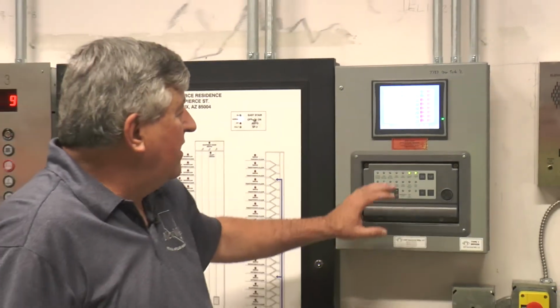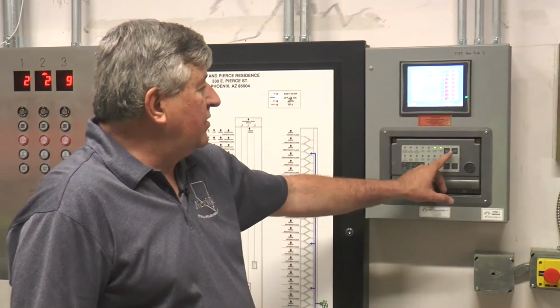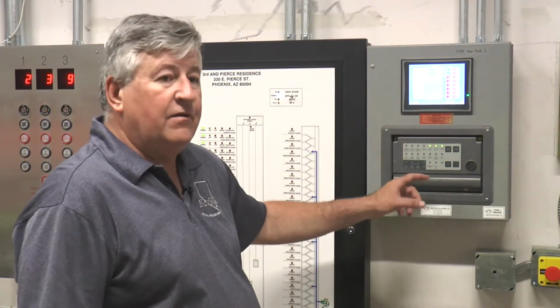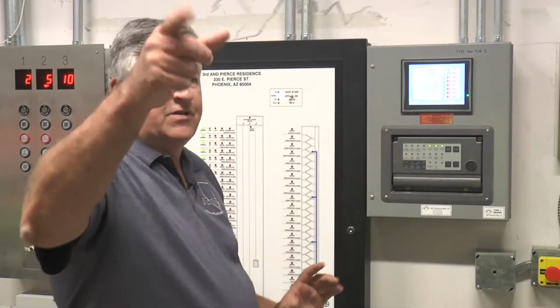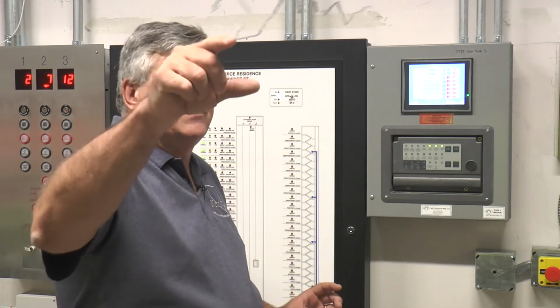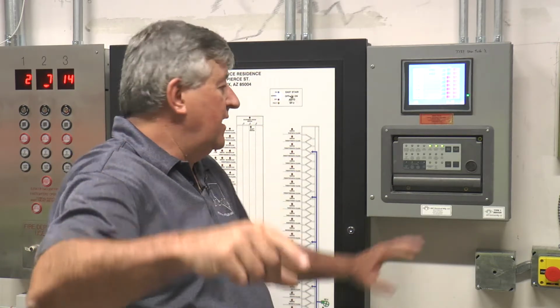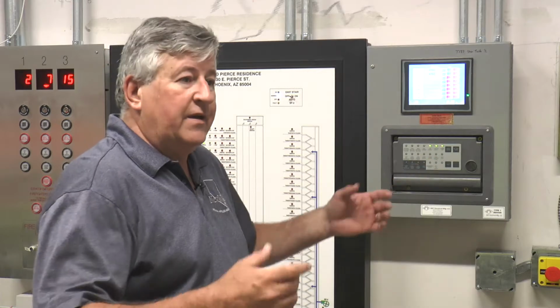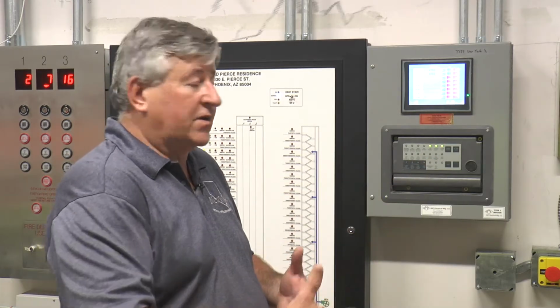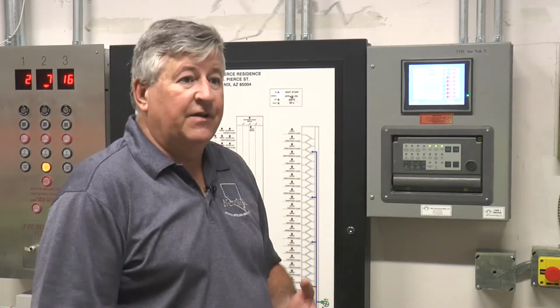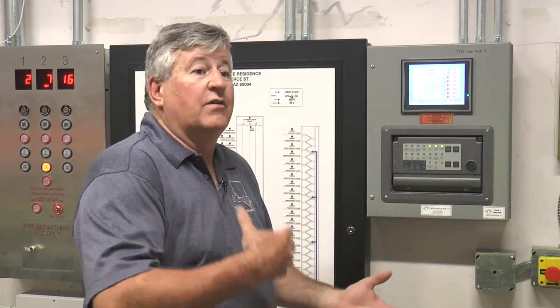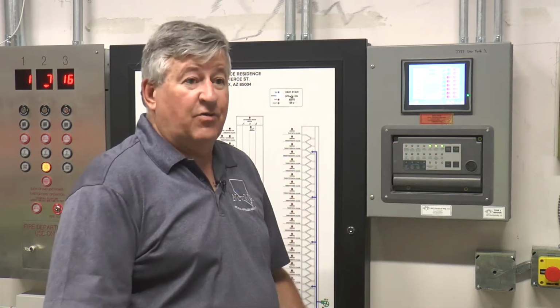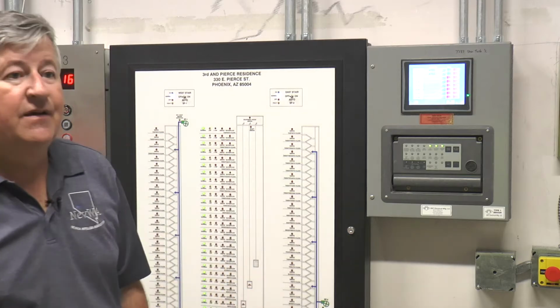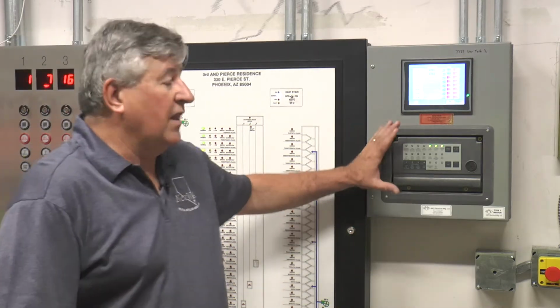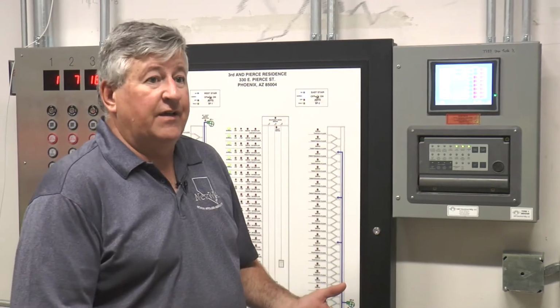But other than that, in the event you have an alarm, you can silence the horn right here. It will silence it here, but it'll still go off at the generator set. Once the fault is corrected, then it will clear it here. But if the fault's not corrected or another fault occurs, the horn will reactivate itself. So you may get someone calling you for a nuisance: Hey, I hear a buzzer in the room and I can't get in there. What's going on? But anytime you hear an alarm, please react to it.